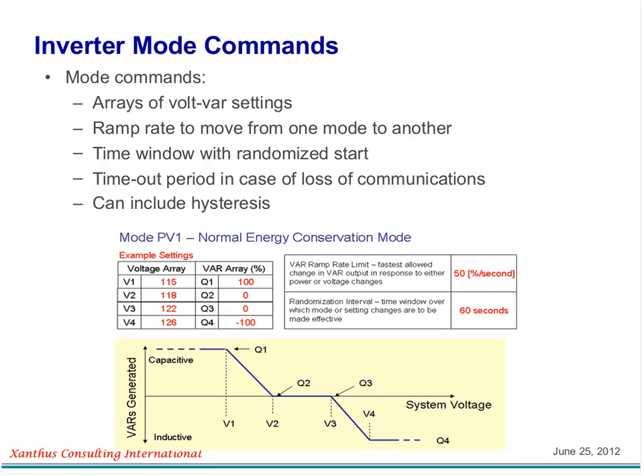Because it's software driven, you can put this right into a little controller. Then you add additional things like ramp rates, a time window within which you randomly make this change. What we don't want is a million of these DER devices suddenly switching all at once—then we'd really have problems with the power system. So we give them a time window, which could be 1 minute, 10 minutes, or 2 hours, depending on what you want to do, and randomly within that time you change the DER to whatever it's being asked to do. Obviously, if you want to shut it off, that's a 0 time window—shut off right now.